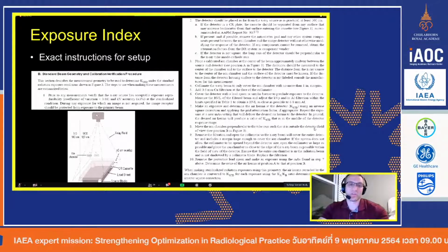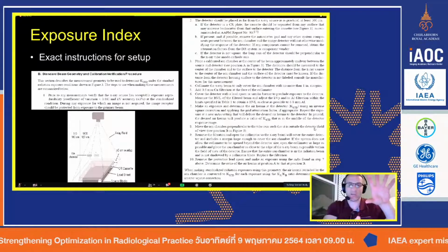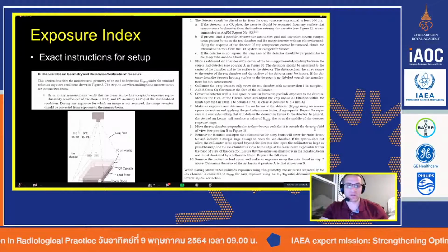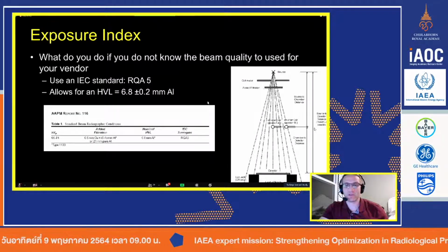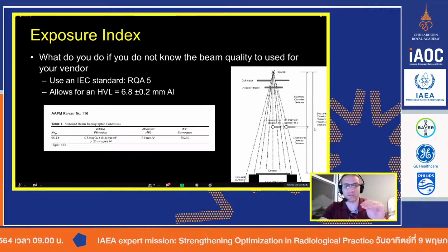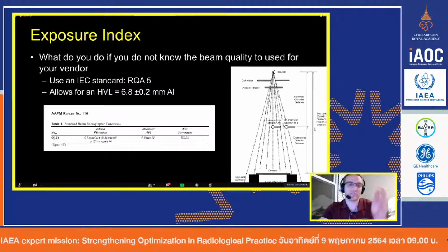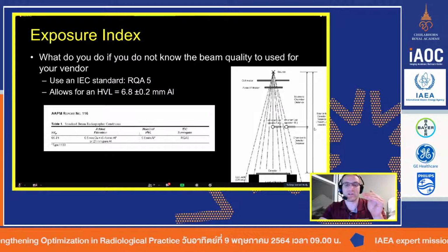But basically what we're doing here is you've got your X-ray tube, you're placing your chamber dead center, and you're going to set it up with a specific distance, like I mentioned. And then you're going to try a couple of different filters. You might start with 0.5 millimeter copper, and you might dial in, say, the middle of that range, 70 kV. And then you'll measure your half value layer.